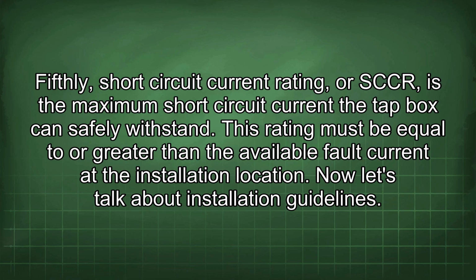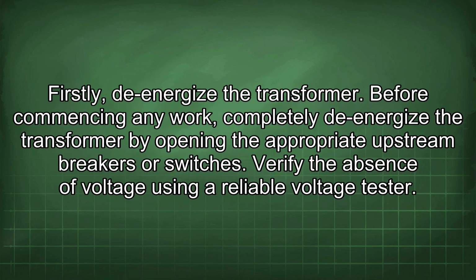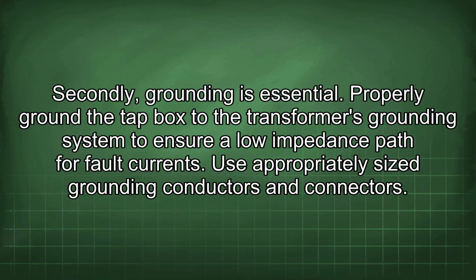Now let's talk about installation guidelines. Firstly, de-energize the transformer. Before commencing any work, completely de-energize the transformer by opening the appropriate upstream breakers or switches. Verify the absence of voltage using a reliable voltage tester. Secondly, grounding is essential. Properly ground the tap box to the transformer's grounding system to ensure a low impedance path for fault currents. Use appropriately sized grounding conductors and connectors.